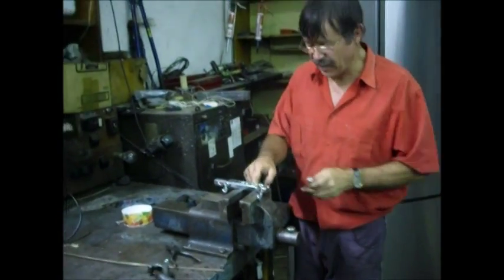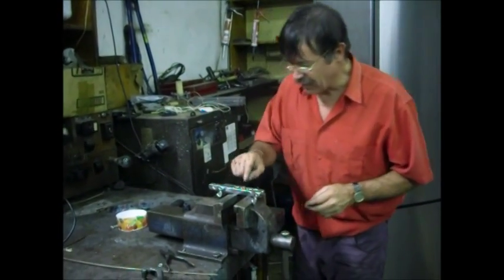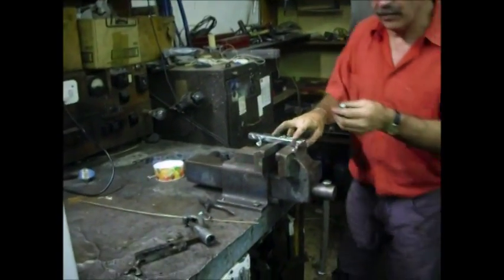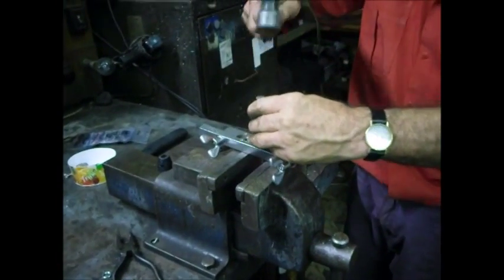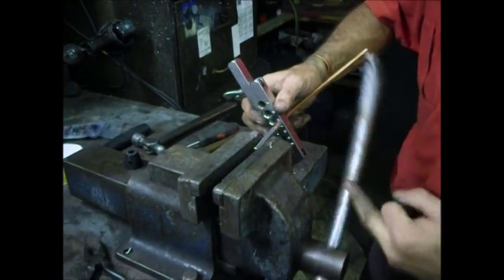This copper pipe has got an internal thickness of a quarter inch and we clamp it in a flaring block and we swage it. We stretch the inside open by hammering this quarter inch swager into it.